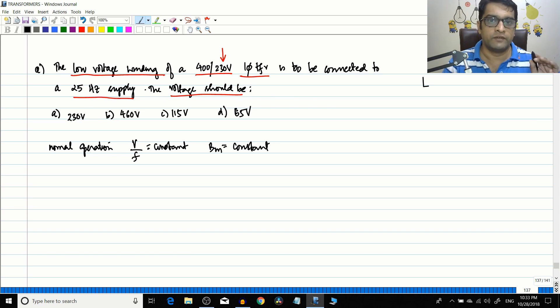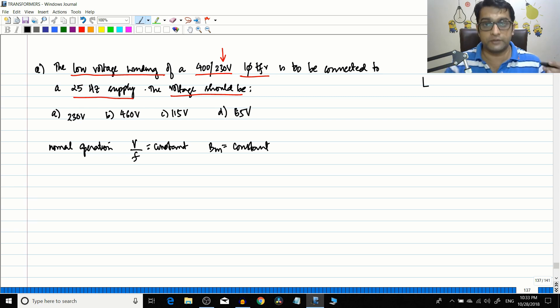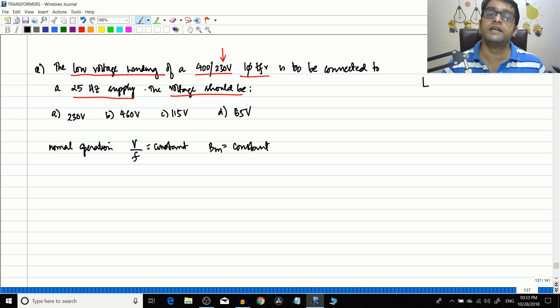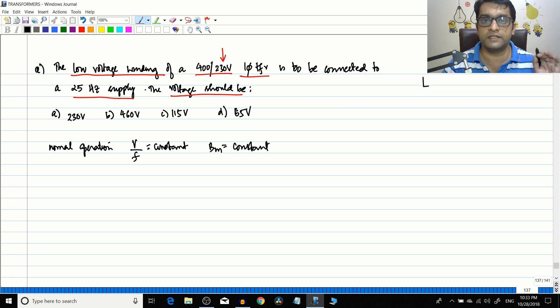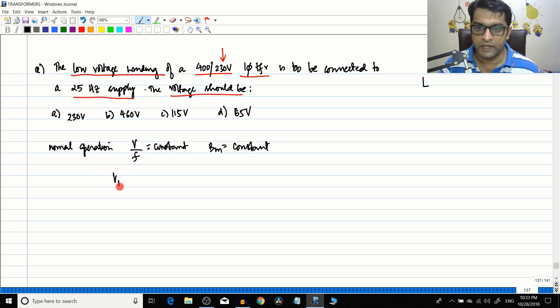If you simply reduce the frequency, the flux will go to a very high value, leading to a very high excitation current, and the transformer will go into deep saturation, causing it to draw far more excitation current than it is rated for. So V/f ratio must be kept constant: V1/f1 should equal V2/f2.